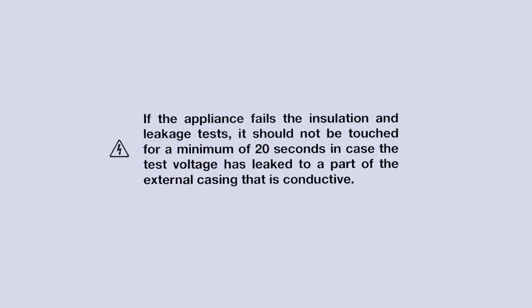If the appliance fails the insulation and leakage tests, it should not be touched for a minimum of 20 seconds in case the test voltage has leaked to a part of the external casing that is conductive.